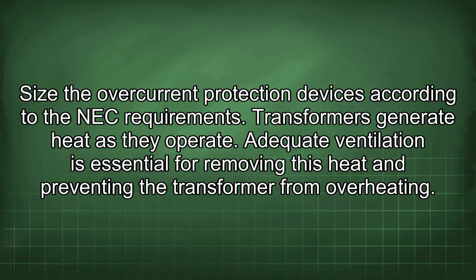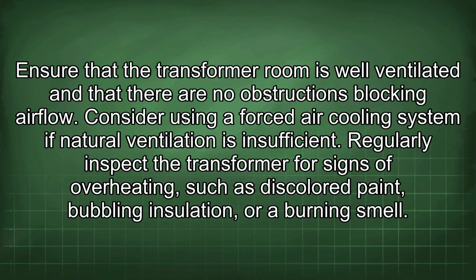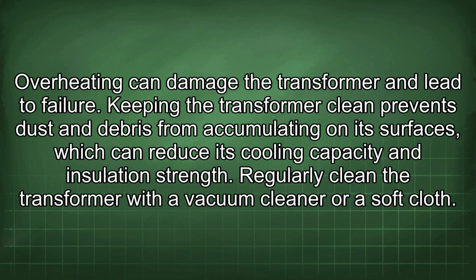Transformers generate heat as they operate. Adequate ventilation is essential for removing this heat and preventing the transformer from overheating. Ensure that the transformer room is well ventilated and that there are no obstructions blocking airflow. Consider using a forced air cooling system if natural ventilation is insufficient. Regularly inspect the transformer for signs of overheating, such as discolored paint, bubbling insulation, or a burning smell. Overheating can damage the transformer and lead to failure.